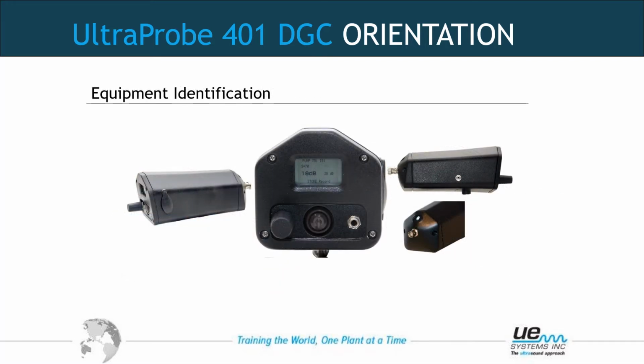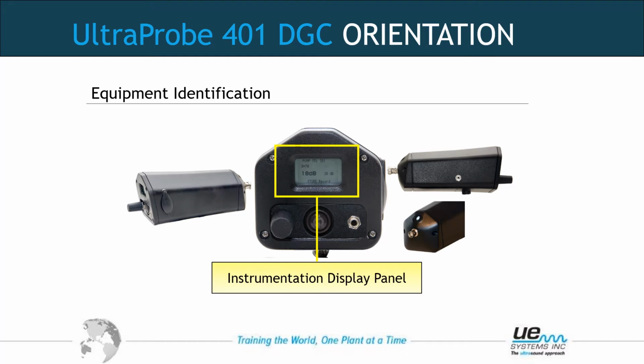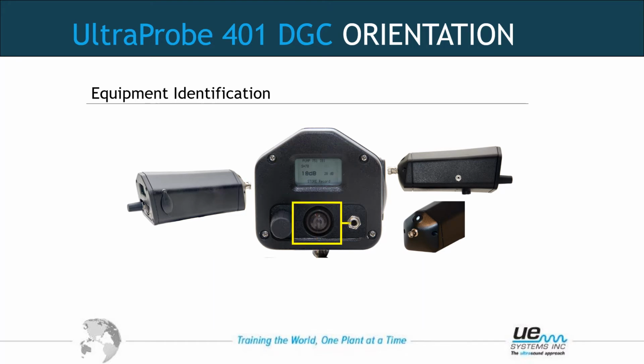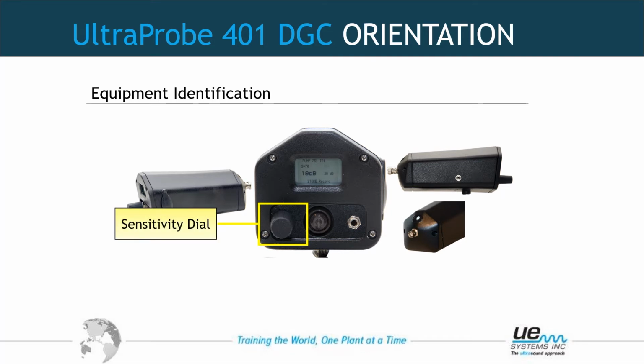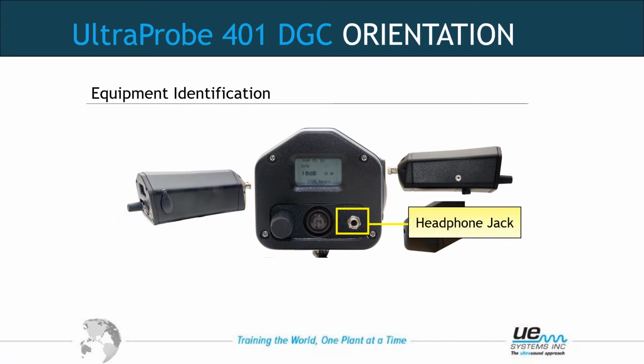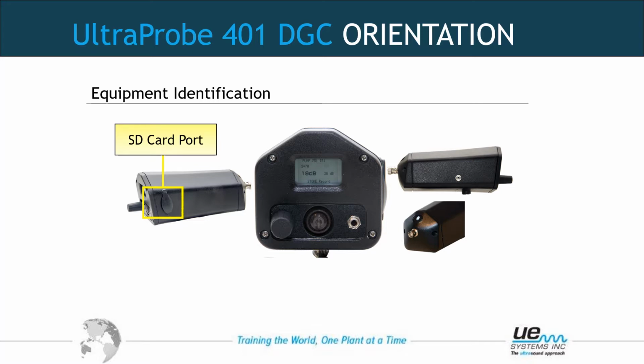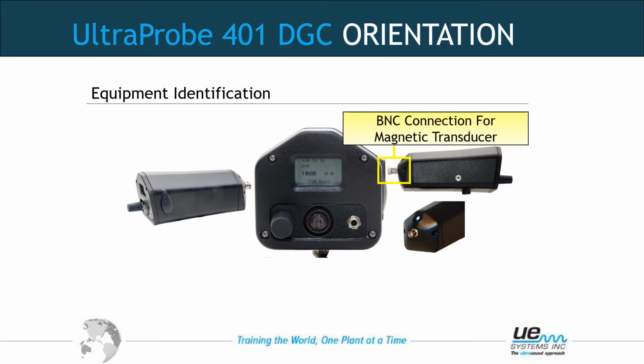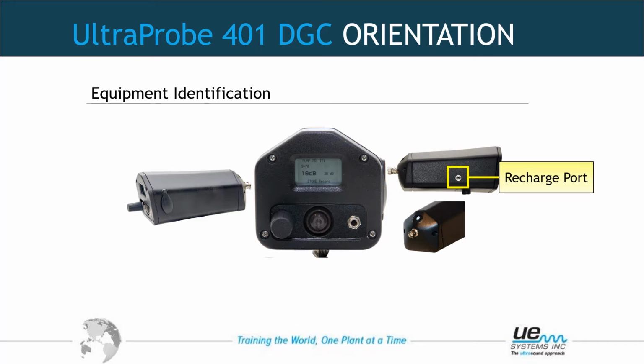Let's go over the different parts of the grease caddy itself. The instrumentation display panel, digital. The on-off button, also used to select some items. The sensitivity adjustment dial, spin and click to select and to adjust. The headphone jack, which is a 3.5 millimeter mono split headphone jack. The SD card port, which does have a cover to keep dirt and other contaminants out. The BNC connection for the magnetic transducer. The charge port. An LED light.